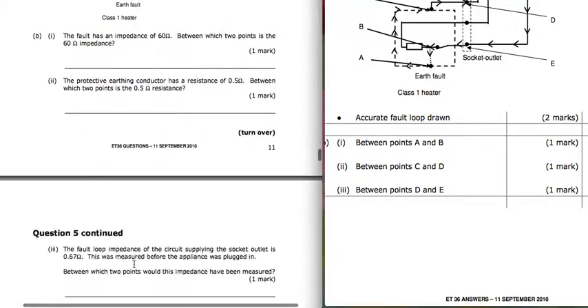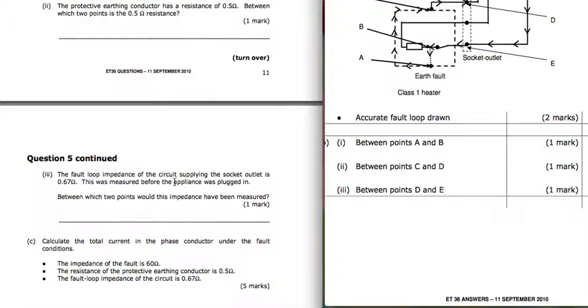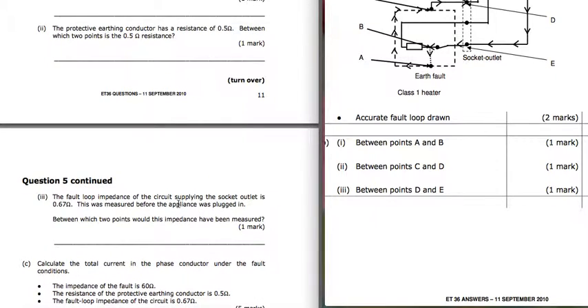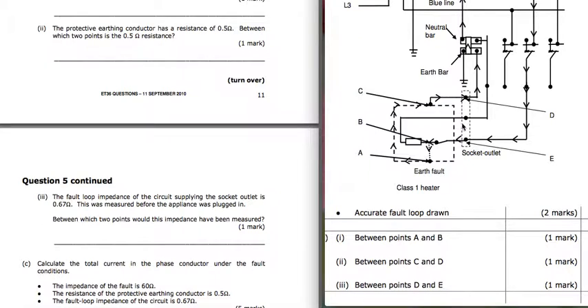And the fault loop impedance of the circuit supplying the socket outlet is 0.67. This was measured before the appliance was plugged in. So it's before this was plugged in here. Between which 2 points would the impedance have been measured? So they would have had to measure it between D and E. So that would have been measuring the fault loop impedance back there. So between D and E.